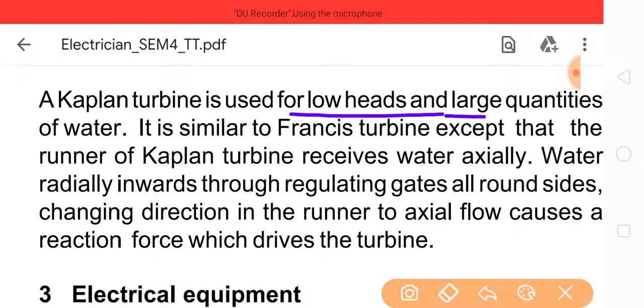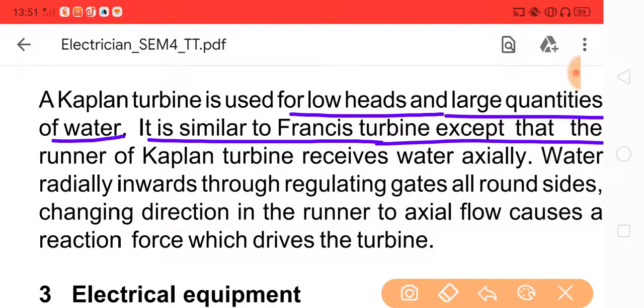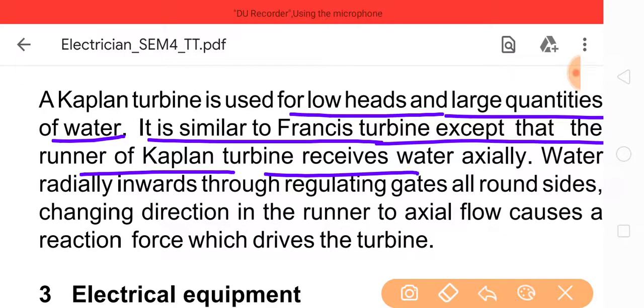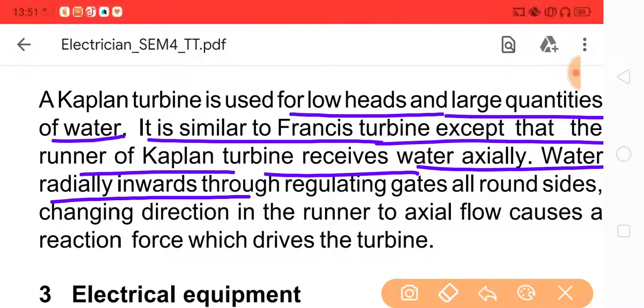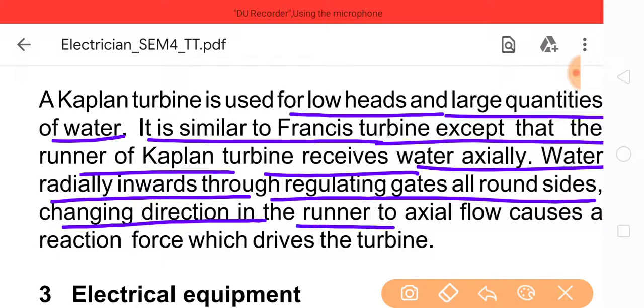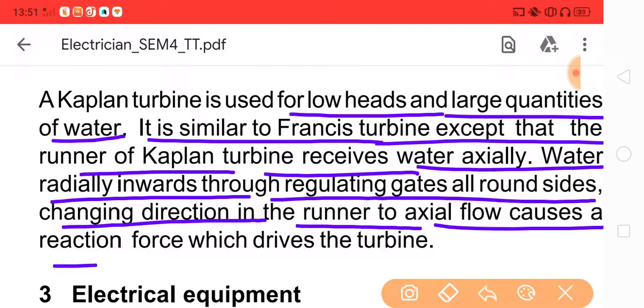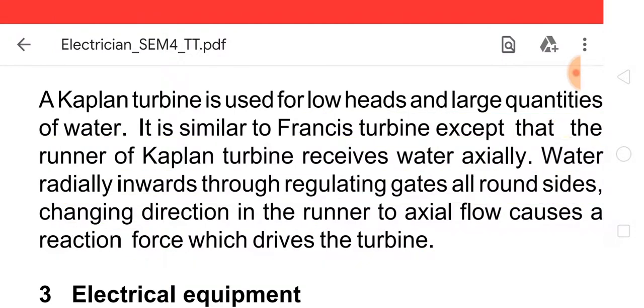A Kaplan turbine is used for low head and a large quantity of water. It is similar to a Francis turbine except that the runner of a Kaplan turbine receives water radially inwards through regulating gates all round the periphery. A change in direction in the runner to axial flow causes a reaction force which drives the turbine.